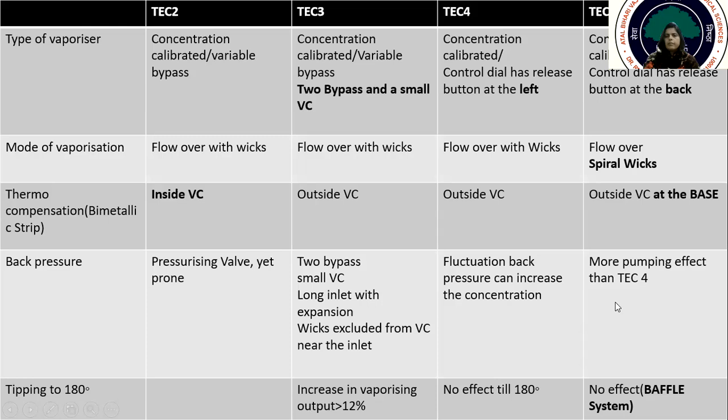And in TEC 5, you will be surprised that though they have used IPPV assembly to reduce the back pressure effect, yet it has more pumping effect than the TEC 4 vaporizer. Now, what about tipping to 180 degrees?